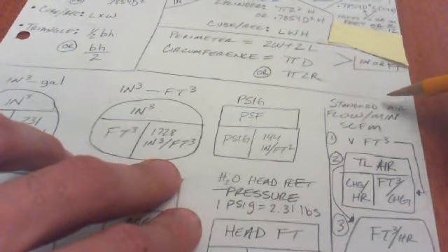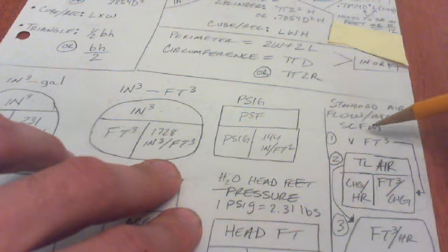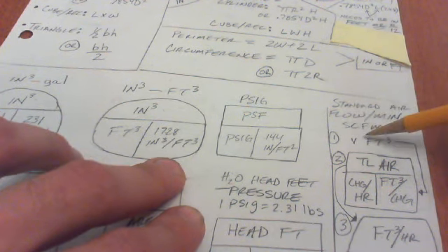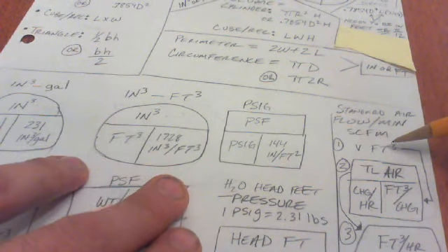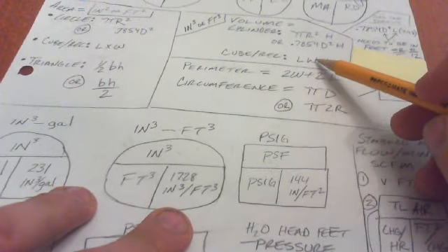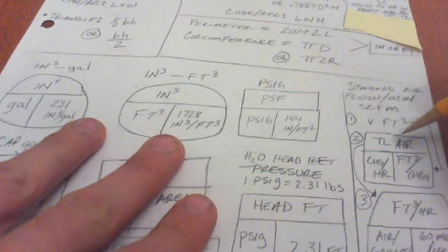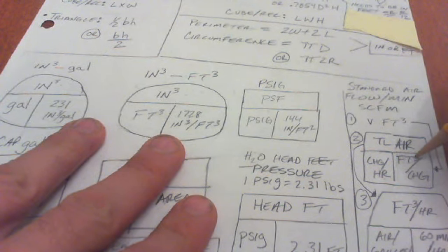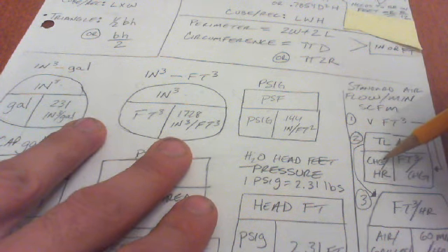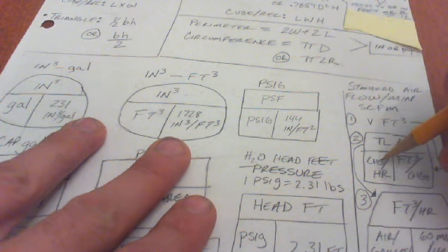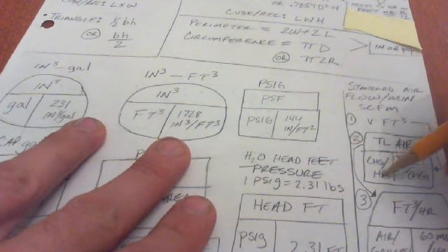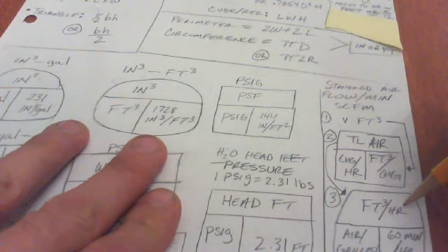Alright. For standard cubic feet per minute, or SCFM, I broke it down into 3 steps. First was define the volume in cubic feet, which is more than likely going to be this one here. And once you got that, plug that into cubic foot per change. And then this would be a given. In the book they gave us that info there, the changes per hour. Plug that in and that'll give us our total air. Total air becomes cubic feet per hour.